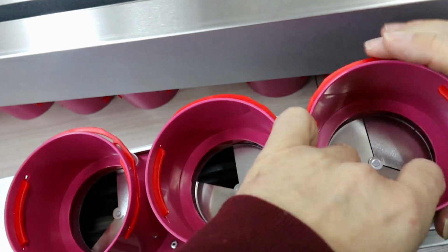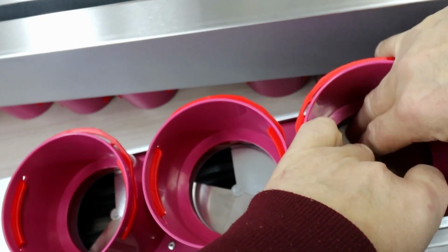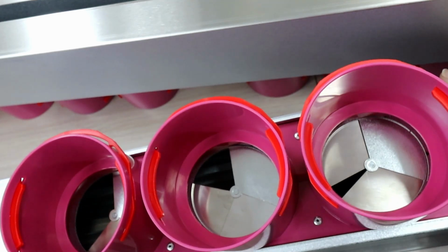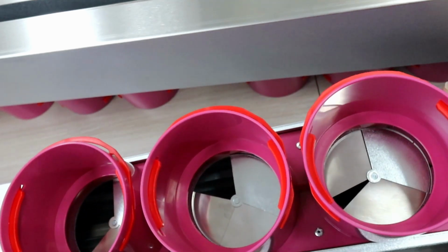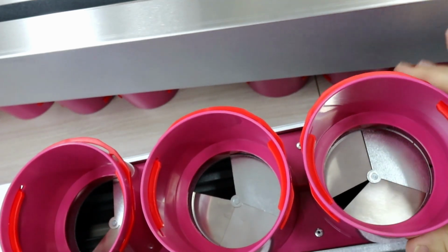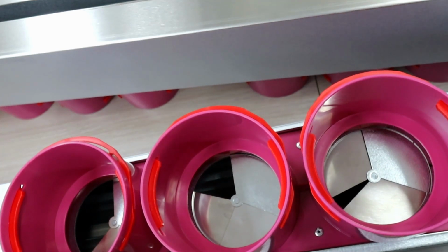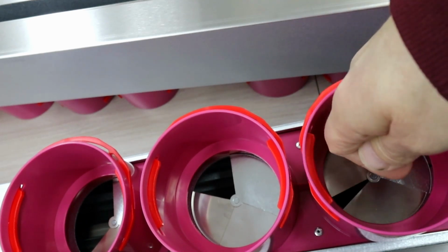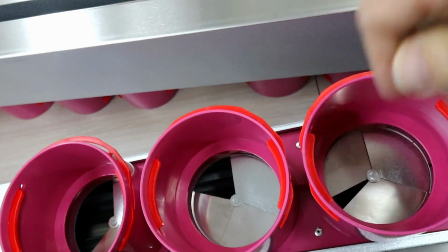Just to touch. Only there always needs to be a slightly bigger gap because if it's too small we might get some noise. You see? Something like this. This is for adjusting the flow. This is what I told you about our dampers used in diffusers. You can do it differently. You can take chairs and take say a rubber mat to seal this opening and simply make smaller holes, and you will also have flow adjustment this way.